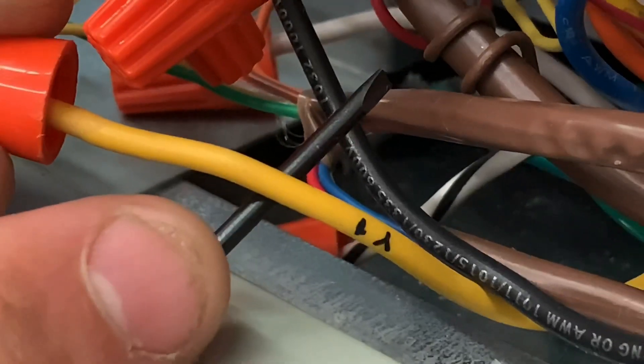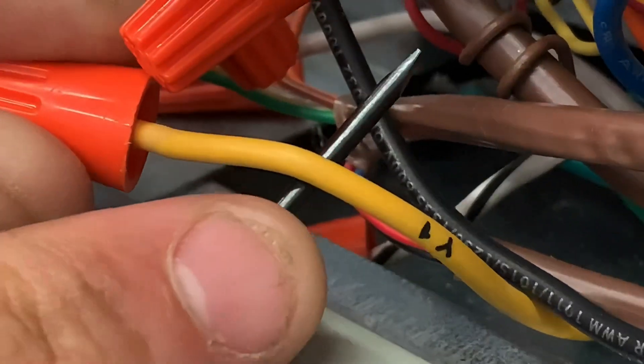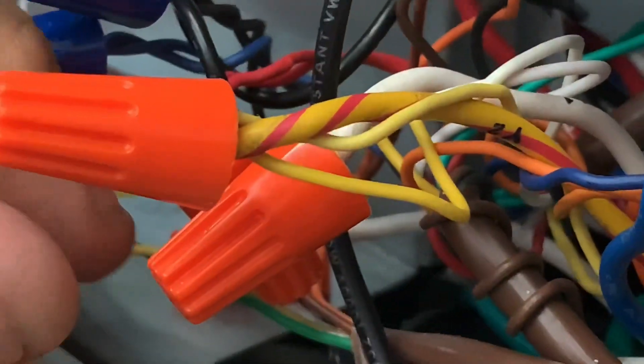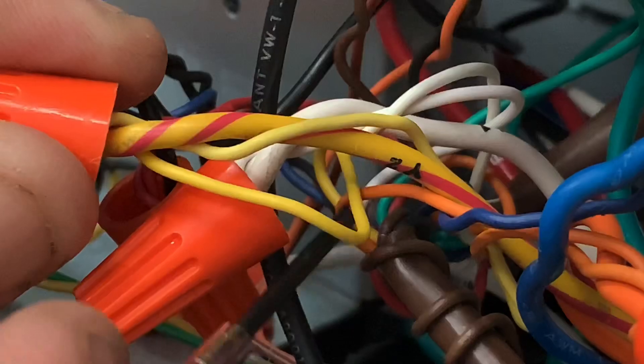But the goal is, if you were to be doing a startup on a single-stage unit, make sure you hook Y from your thermostat to that Y2. We're not going to use Y1, we just got a wire nut on it.